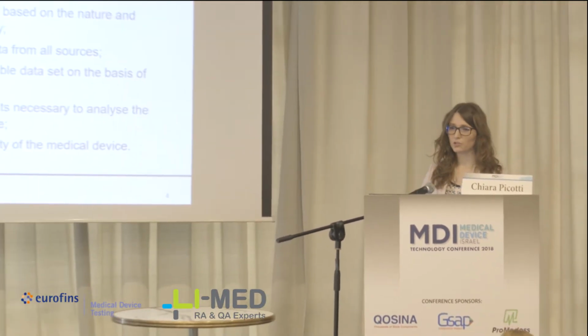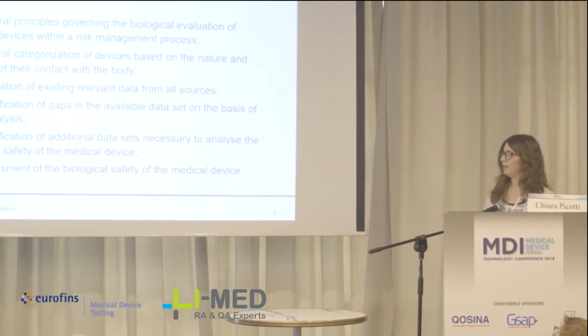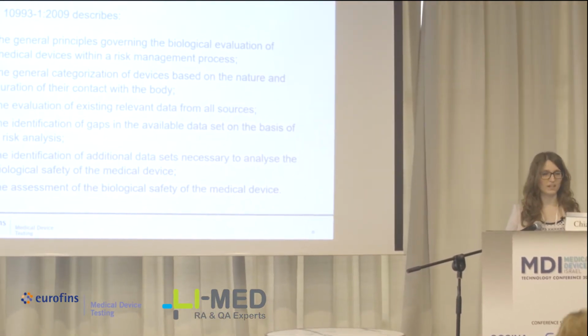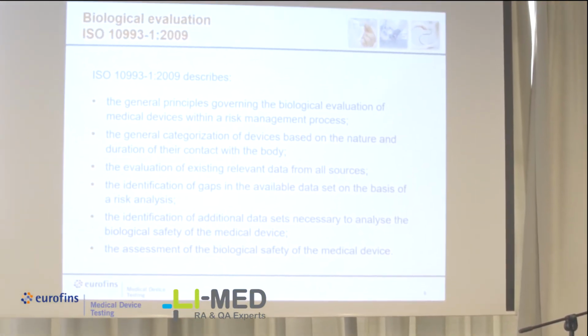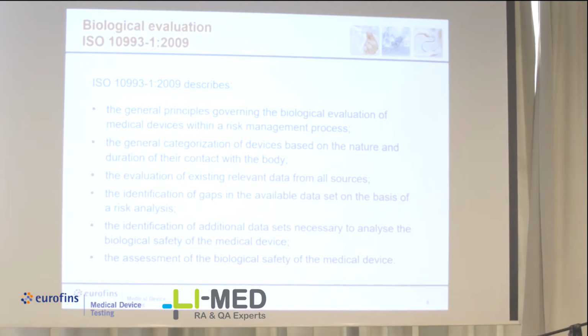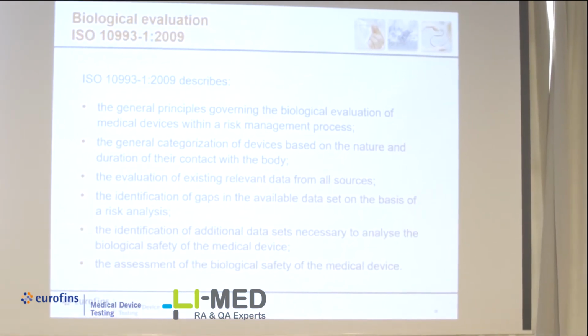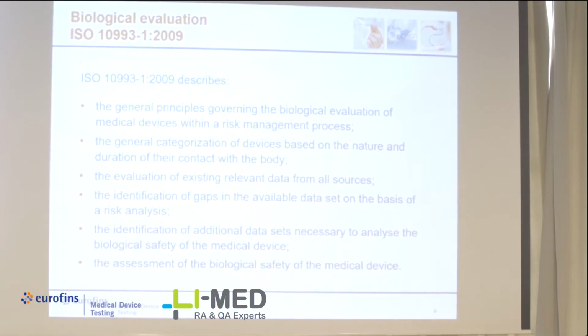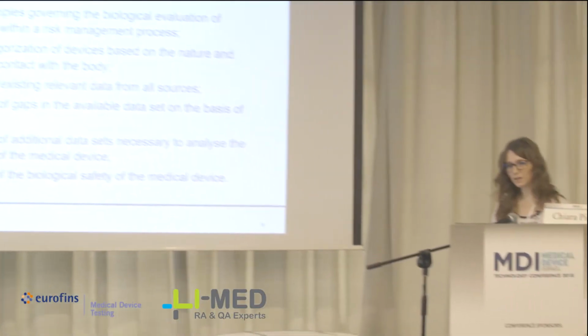But what is the ISO 10993-1? It's a horizontal standard, so it means that it can be applied to all medical devices, to the whole categories of medical devices. It was issued in 2009 and basically describes the general principles that govern the biological evaluation, which is considered a part of a structured program within a risk management process according to ISO 14971. And thanks to this part of the ISO 10993, we can identify the categorization of medical devices according to the nature of contact and the time of contact.